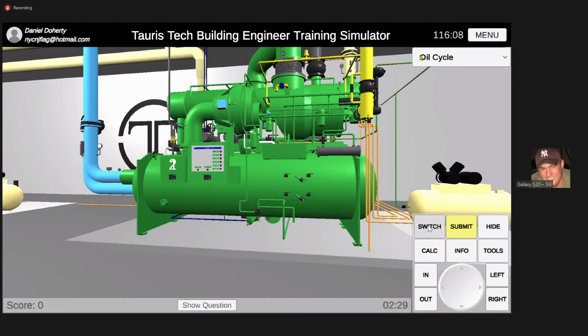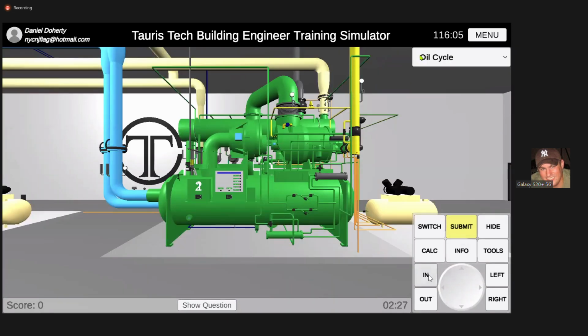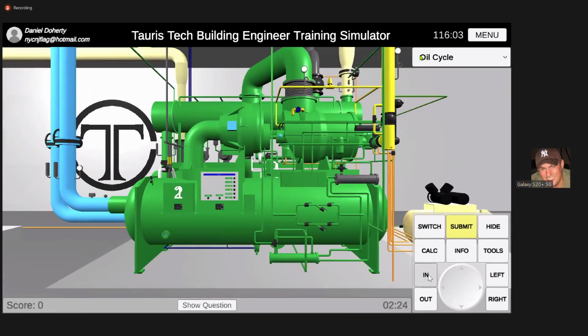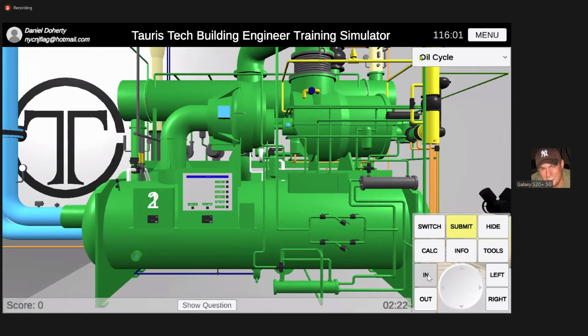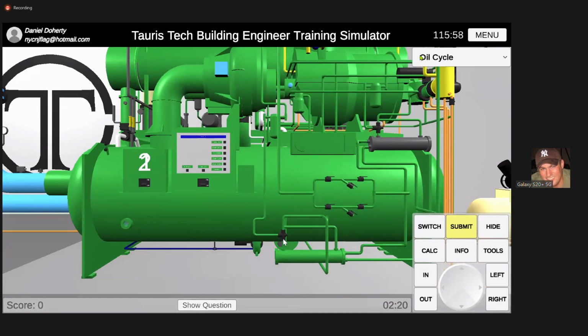And then, like I said before, now going back to it with everything back, you have a thermal valve. You have two thermal valves. You have a thermal valve on your compressor oil cooling cycle, and a thermal valve on your turbine oil cooling cycle. So if you follow the water, it goes here. We're going to do the compressor one first. The water comes in through your manifold, comes out the manifold, and it supplies the oil heat exchanger, okay? And it comes out this way.